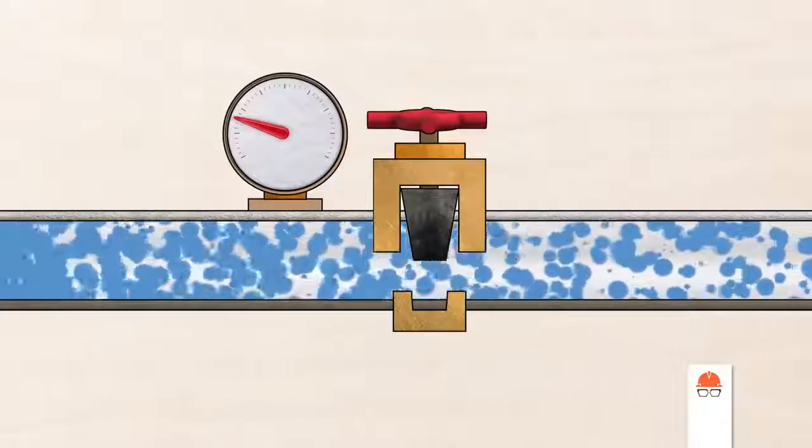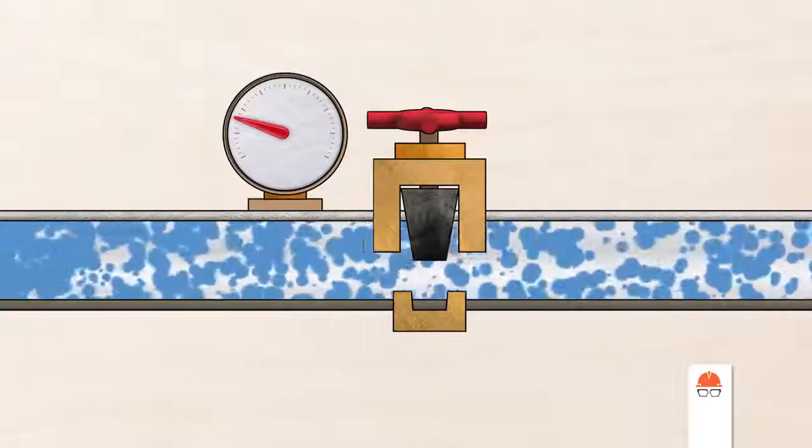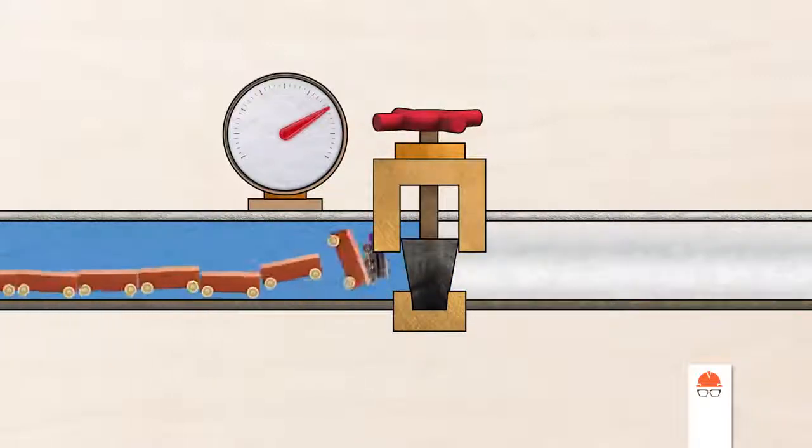Imagine you're an operator at the end of this pipeline in charge of closing a valve. If you close it quickly, you've essentially slammed those trains into a brick wall, and the pressure spike that results from such a sudden change in momentum can rupture the pipe or cause serious damage to other parts of the system. There's actually another term for when a large spike in pressure ruptures a sealed container: a bomb, and water hammer can be equally as dangerous.